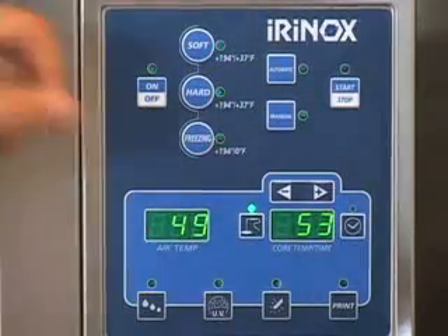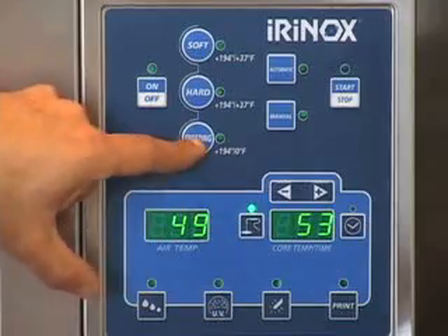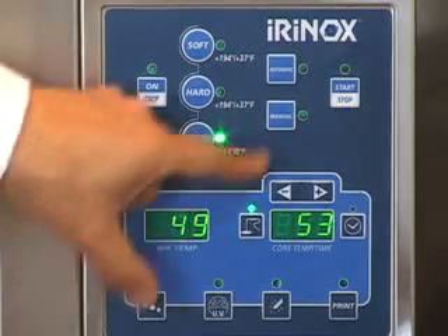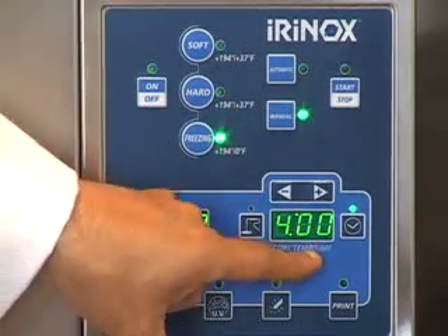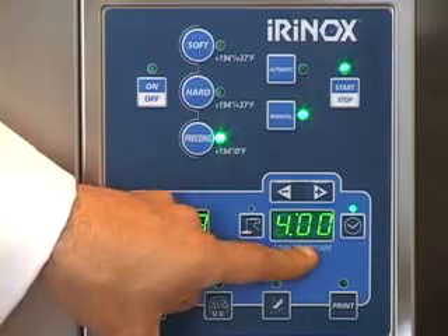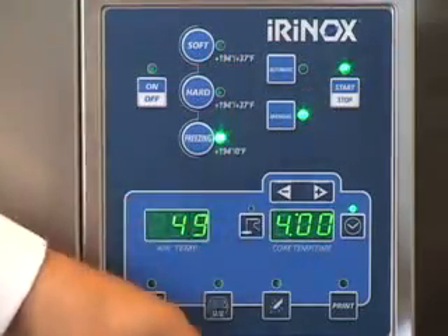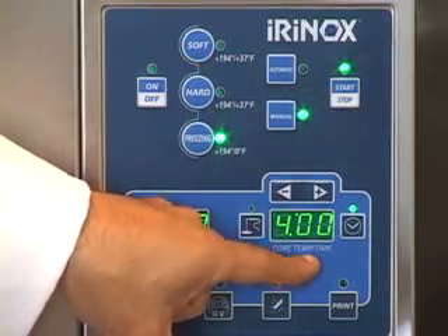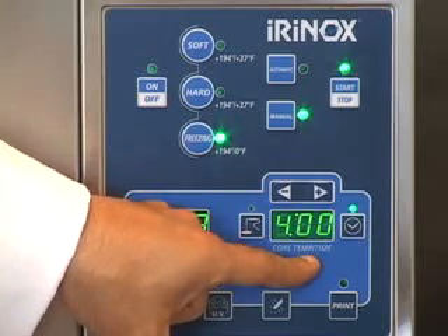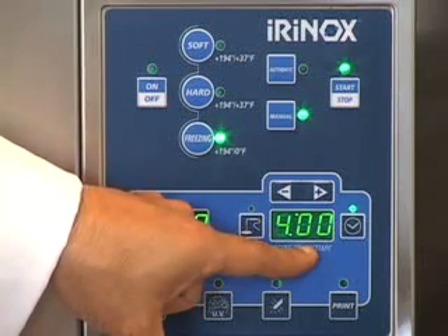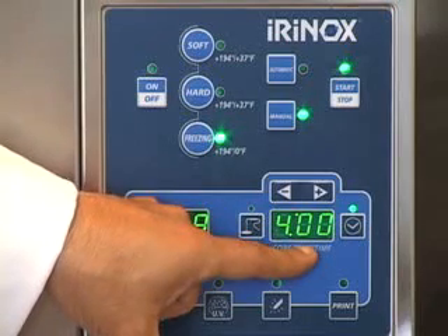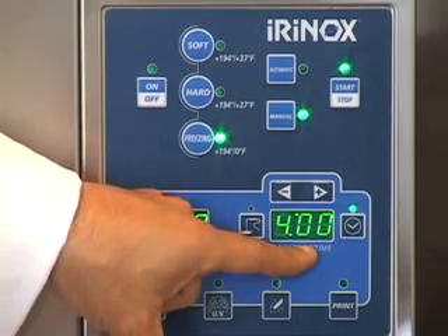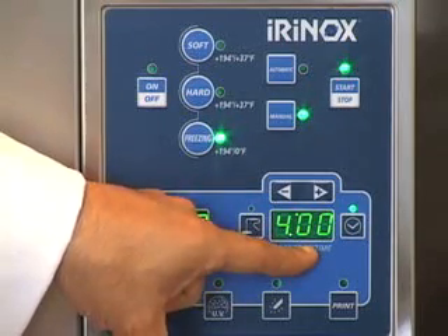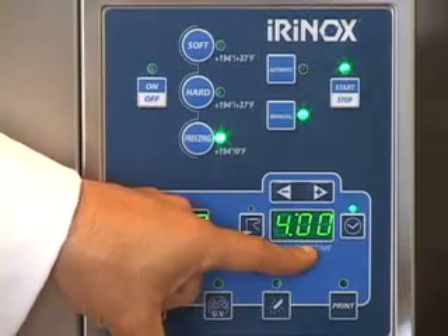I'm now going to demonstrate the shock freeze manual mode. I select the shock freeze cycle and the manual cycle. As you can see, the time is showing 4 hours. When I hit the start button, the unit is going to run from -30 to -40 degrees Fahrenheit for 4 hours and then go to 0 degrees in hold mode until I stop the unit. Again, you have to verify that your product has gotten to the temperature that you want it at before removing it.